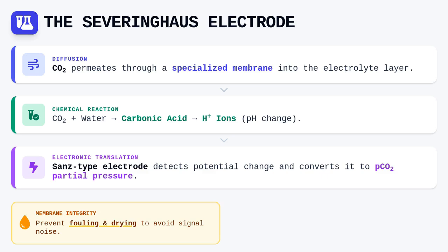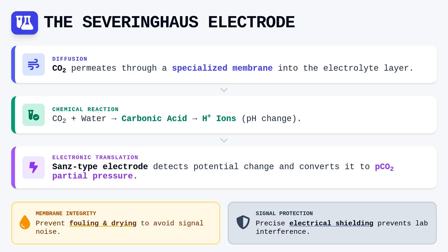Maintaining the membrane's integrity and hydration is paramount, as the drying of the electrolyte or membrane fouling effectively increases response time and degrades the signal-to-noise ratio. Precise electrical shielding is necessary throughout all these circuits to prevent the introduction of interference from the surrounding laboratory equipment.